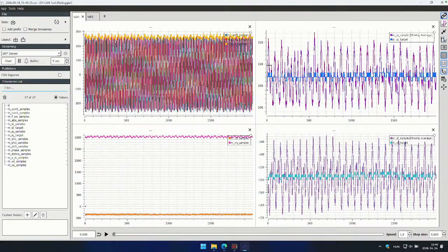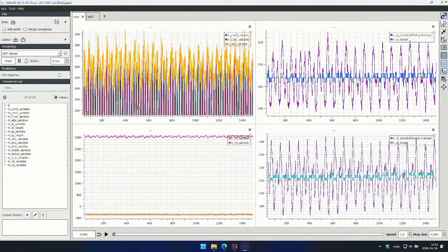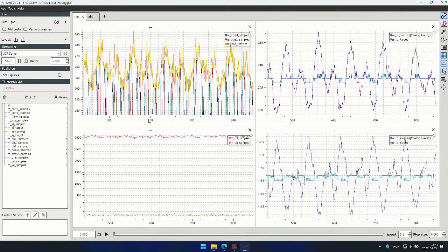Here you can see some oscillations, but not too much — from 20 amp to 21.5 amp. We could decrease it with another encoder nonlinearity calibration at a different point, which might give better results, but these are pretty good and not critical waveforms at all.